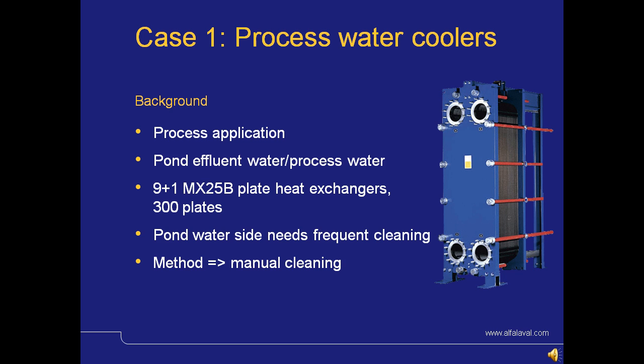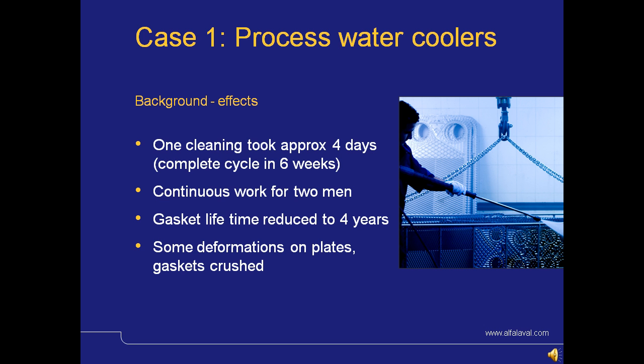The pond water side needs frequent cleaning, and the method used by the customer was manual cleaning, meaning that they opened each heat exchanger when needed and they cleaned every plate, plate by plate. One of these cleanings took approximately 4 days. The complete cycle was done in 6 weeks, meaning that they took down 1 heat exchanger, cleaned it, closed it back up, opened another one, and so on. They did all of this in sequence. This was more or less continuous work for 2 men.